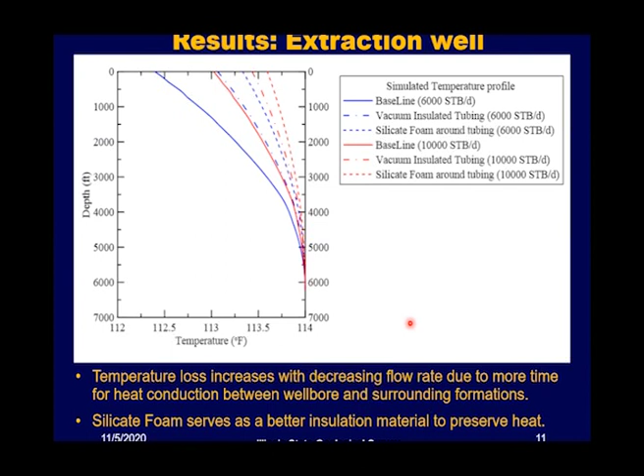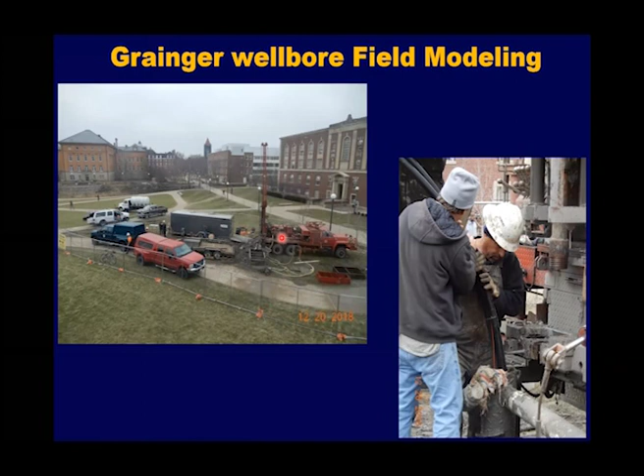Then we switch to the injection wells. The temperature difference between the injection temperature and the average temperature of the soil profile influences the temperature at the outlet linearly. Then we switch to the Grainger wellbore field modeling. For this site, the red color here shows the drilling of one borehole. Later, we'll measure the temperature data in this borehole and compare it with the simulated result. Here's the configuration of the well group on the site. There are 40 wells installed on the site, and you can see in the figure green tunnels and pipes that have been running for around 140 years. These tunnels and pipes provide an actual heat source heating the ground, and we want to get the initial ground temperature contours by considering the heat from these pipes and tunnels first.